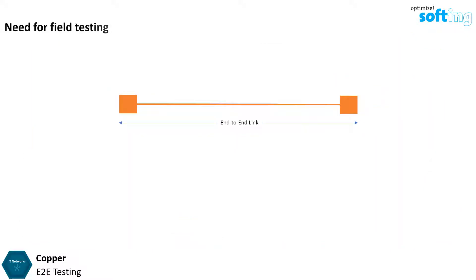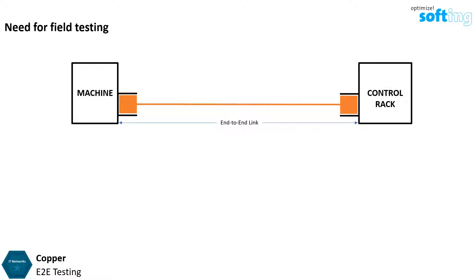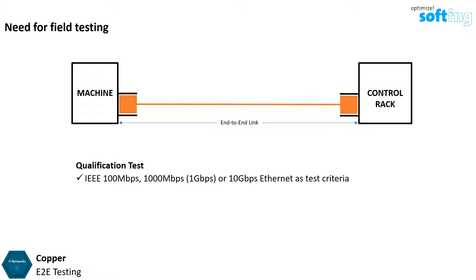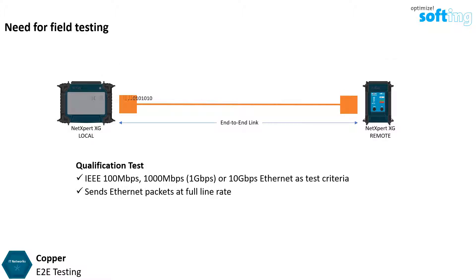Since it is very common in industrial applications to build a customized link — for example, between a machine and the control rack — field termination of the plugs of the end-to-end link becomes important. There are two methods to perform field testing that can be applied for end-to-end links. Qualification test uses the IEEE 100Mbps, 1000Mbps, or 10Gbps Ethernet as a test criteria.